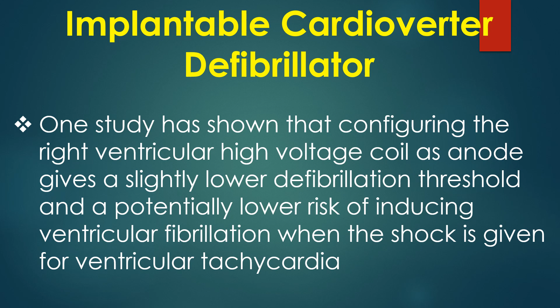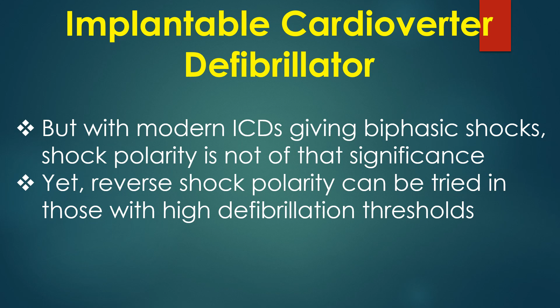Multiple shock vectors can be programmed because the CAN and both high voltage coils can act as electrodes for discharging the high voltage shocks. One study has shown that configuring the right ventricular high voltage coil as anode gives a slightly lower defibrillation threshold and a potentially lower risk of inducing ventricular fibrillation when the shock is given for ventricular tachycardia. But with modern ICDs giving biphasic shocks, shock polarity is not of that significance. Yet, reverse shock polarity can be tried in those with high defibrillation thresholds.